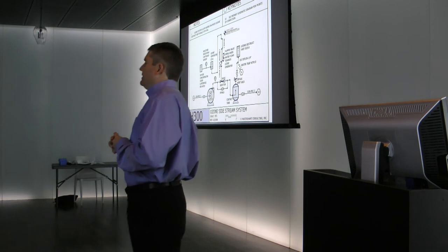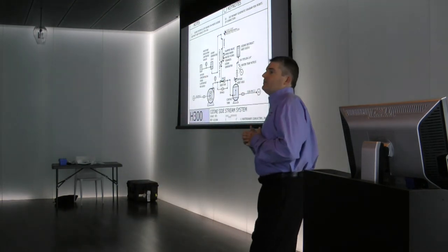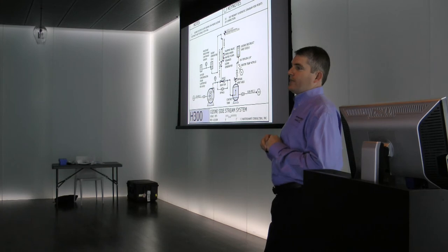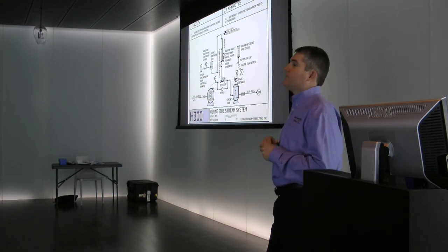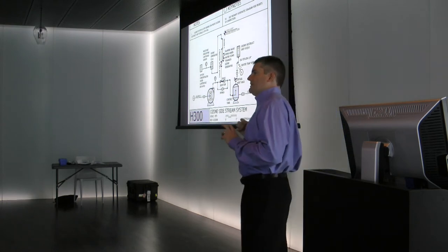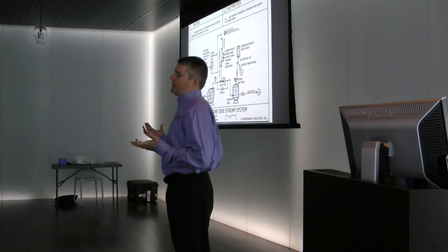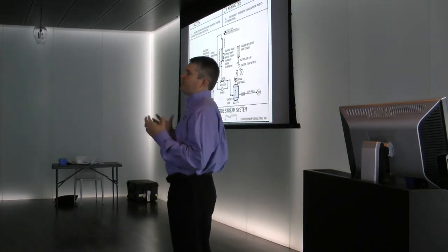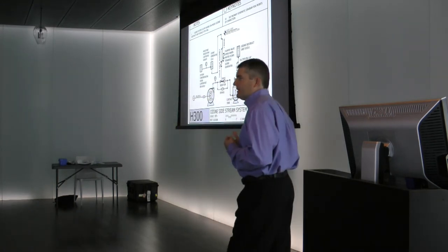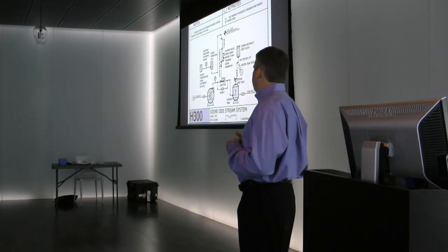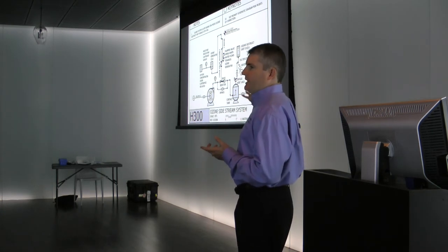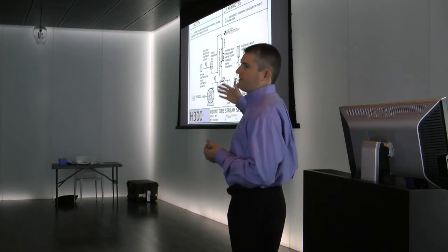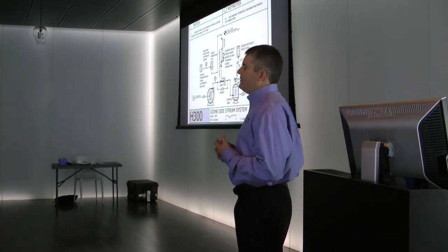Right. Now, that being said, we've actually done systems that are chlorine-free and they just run on ozone, and you can't smell the ozone, but you can detect it in the water. Normally with ozone, you would want to maintain a residual of chlorine in the water. Now you could reduce that. Instead of having 2 parts per million chlorine, you could be down at 0.5 part, which would be much better for you, because you're going to let the ozone do all the work back in the filtration system. And assuming that you've designed that correctly and your system's efficient, that this will handle it.